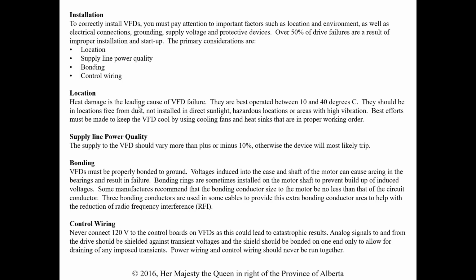Supply line power quality, again, we want to be within 10%, otherwise the device will most likely trip. Bonding, again, here's where it talks about the voltages induced. They must be properly bonded so that the voltages induced in the case and shaft of the motor don't cause arcing in the bearings and result in failure. Bonding rings are sometimes installed on the motor shaft to prevent buildup. And some manufacturers recommend that the bonding conductor size be not less than that of the circuit conductor. So again, that large size. And then sometimes, again, they say 3 bonding conductors are used in some cables to provide extra bonding conductor area to help with reduction of radio frequency interference, or RFI.